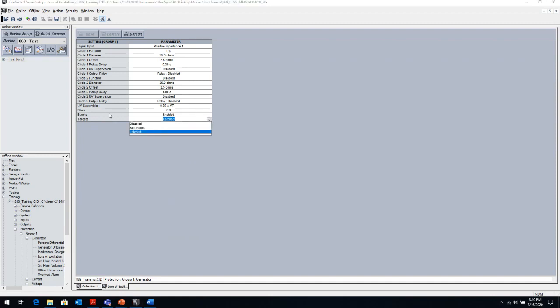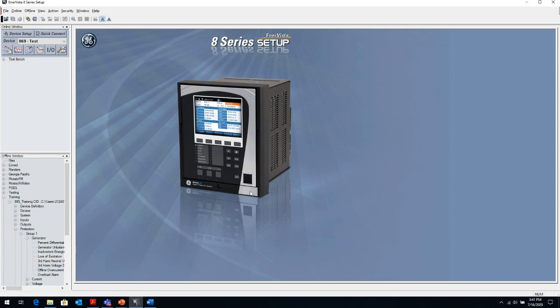Depending on the type of element that you're enabling, if it's a tripping element, I usually recommend setting the targets to latch for any tripping element because you want to see what element tripped the relay. Because if you set it to self-reset, if the breaker opens up and say it's an overcurrent condition and that overcurrent goes away, then those elements will reset. You go in front of the relay, you will not know what caused that trip because those elements have reset. And then you would have to go into the sequence of events and look in the time stamps to see when that relay tripped and what elements tripped during that time. Whereas if you have a latch condition, when you go in front of the relay or you access the relay remotely following an event, you'll see all of the latched elements that are up on the relay to tell what has caused the trip. And when you press the reset button, whether locally or remotely on the relay, then it will unlatch those latch conditions.